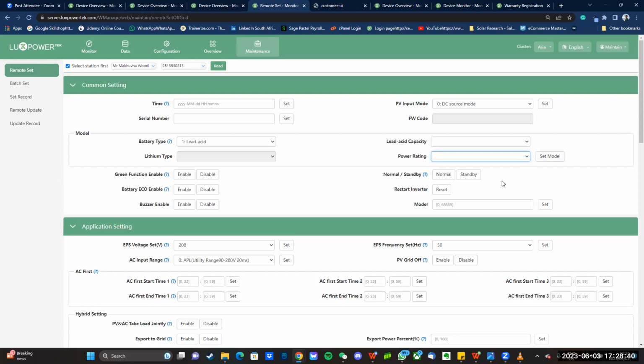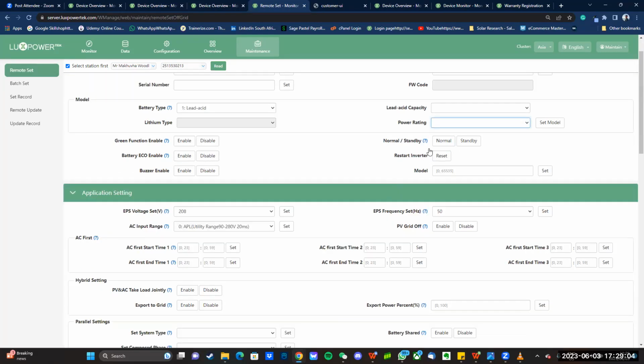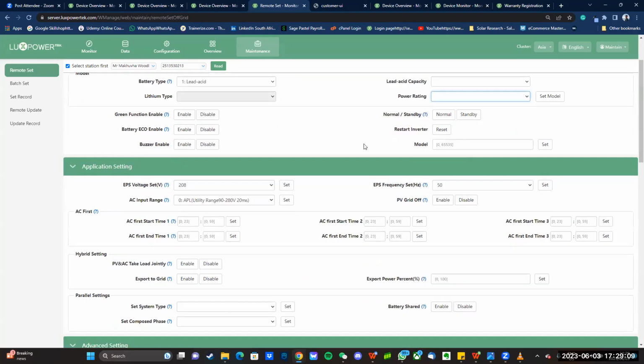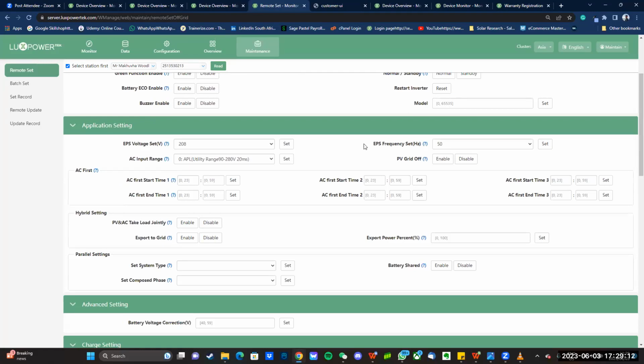Now what will happen is, I can't remember the exact minutes, but let's say every 10 to 15 minutes, the inverter will automatically troubleshoot itself to see if that fault or warning is still present. If not, it'll just remove that fault code, and that applies to all of the other faults and warnings as well. Okay, you've got your restart inverter button over here, and then going down to your application settings. Get a lot of questions on this. How do we know which AC input range to use? So I'll get to that now.